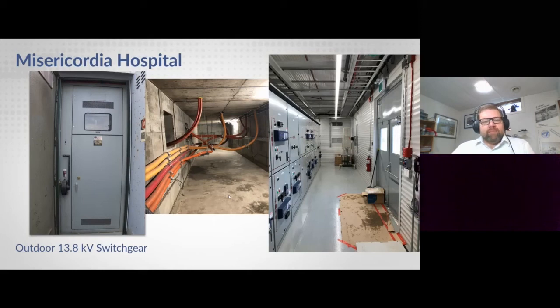Now this was the nice feature. We designed the new substation building, shown on the right-hand side of this photograph. We built everything and fed cables into the tunnel in the middle. So all we had to do was cut, splice, and test those cables, and we were back up and running. While the hospital ran on backup power, we had already pulled in all the cables, so we cut, spliced, and moved on.